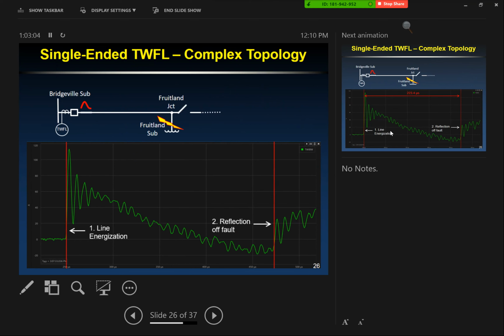So maybe you're gonna talk about this later, but I would assume Fruitland tap would be smaller conductor than Bridgeville. Yeah, and I don't see much effect in that. Your characteristic impedance is not going to change a whole lot from different conductor types that I've seen. But anytime you have a junction point, now you've got half of the characteristic impedance that you had before. So you definitely see those reflections. That's what I was gonna say, the impedance difference between two different wire sizes is relatively small compared to that junction point, the parallel of two impedances at that junction. Right. If you hit an end point that looks like an open, or you hit a junction or transformer, something like that, that's much more significant than just a conductor section.